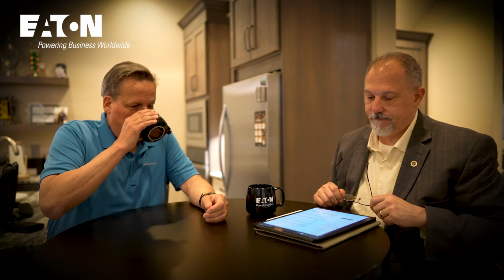210.8A is dwelling units. Now, what does that tell us? That tells us we're talking about GFCIs in dwelling units only. And parent text of 210.8A is going to set the stage for all of the locations, all the list items. Here we go. All 125 volt through 250 volt receptacles installed in the following locations and supplied by single-phase branch circuits rated 150 volts or less to ground shall have ground fault circuit interrupter protection for personnel.